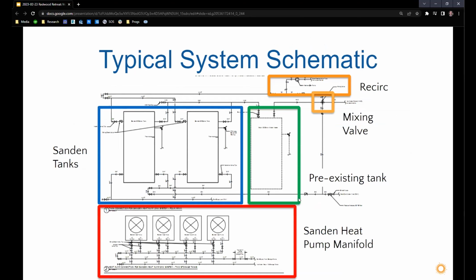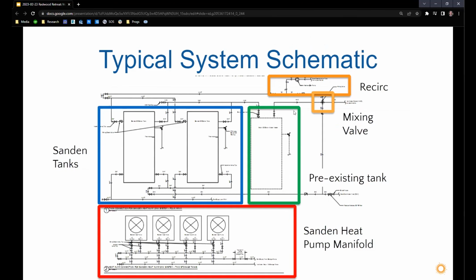With these projects, these initial Mercy projects, we actually used a pre-existing gas-fired swing tank, which is a hybrid design, kind of like a swing tank would be now, where you use electricity. In those days, we kept the existing equipment they had on site, and we utilized the heat pumps to preheat that, and then the gas boiler was kind of our gas peaker plant. Today, we're not doing that sort of thing. We're putting in an electric swing tank, but that had its advantages in terms of reducing the costs. And so that's pictured in green there.